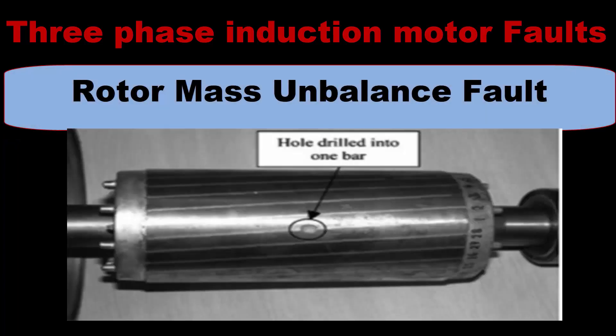Rotor mass unbalance fault: the rotor of an induction motor is placed inside the stator and rotates coaxially with it. In healthy motors, it is centrally aligned with the stator, and its axis of rotation is the same as the geometrical axis of the stator, so the air gap between the inner of the stator and the outer of the rotor is uniform. If this air gap is not the same, then eccentricity occurs, and this rotor fault is called rotor unbalanced fault.